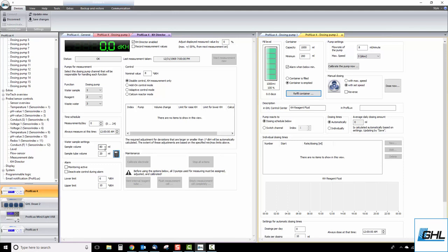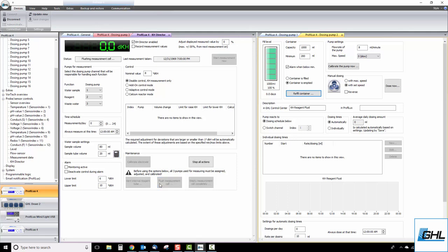Once all those points have been checked, click save changes and then click the flush measurement cell button to allow the KH Director to perform its first water sample flush. At this time, check for any leaks around the probe compression fitting.